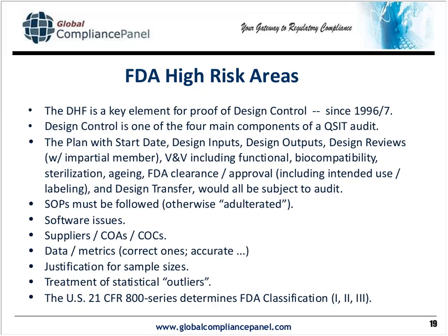But in addition to that, some of the key areas that I found in the past, of course, one of the most obvious gimmes to the FDA is you don't have a design control system in operation. It's not defined by SOP. You're not following your SOP. You don't have a start date. You don't have other issues that are addressed. Now, that middle bullet point is interesting. SOPs must be followed, otherwise adulterated.